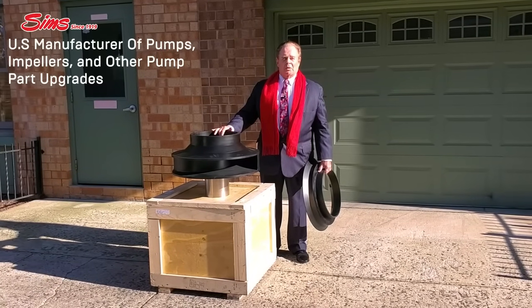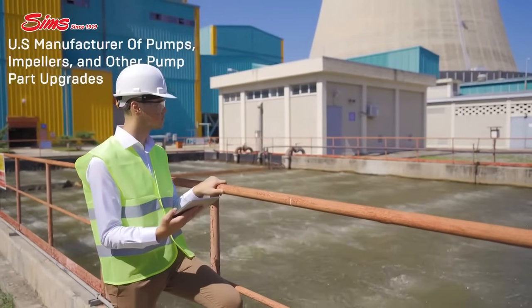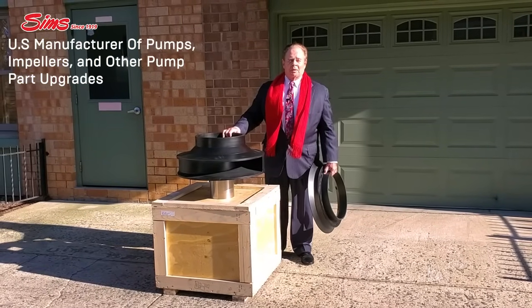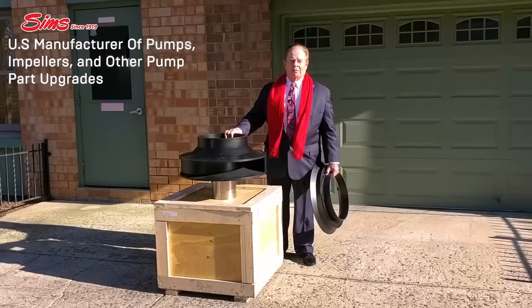This impeller is a wastewater impeller. The original metallic impeller had a huge problem with clogging from debris. Our SimSight engineers redesigned and engineered this. We changed the number of vanes, the vane angle, the vane shape, so it opened up the area so it won't clog from debris.